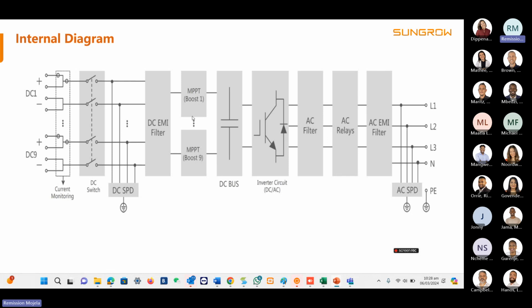If it's the 50, it will have 5 MPPTs. So this is just the basic structure of the 110. Then it goes to the DC bus, goes to the inverter circuit, whereby it changes the DC to AC. You have your AC filter, AC relays, and your AC EMI filter as well. And then the SPD. So basically all the boards in the inverter itself have SPDs for surge protection. And then that's basically it.